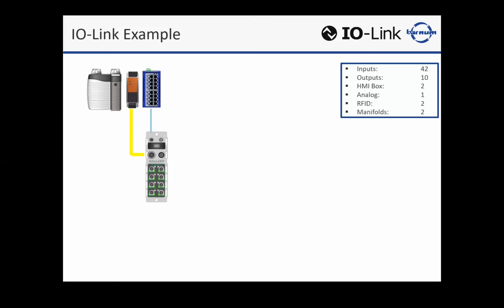I can connect RFID directly to the master block. I do not need a processor. We'll touch base more on that, but I can hardwire an IO link enabled read write head directly to the master block. I can wire directly to valves that have an IO link communication module. I can connect directly to IO link enabled devices that we spoke about, such as sensors, indicators, motion.